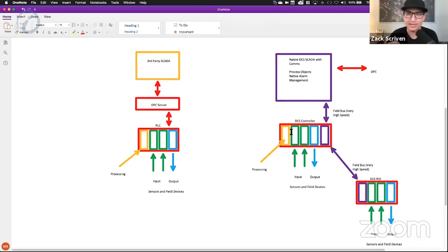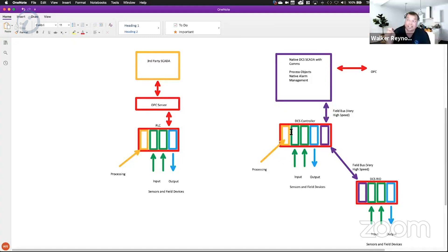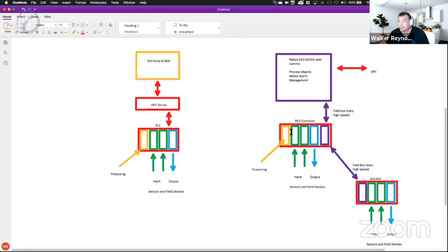This is why some would say that PlantPAx — Rockwell Automation's line of PLCs — makes it DCS-like, because they give you those pre-configured objects that map to their SCADA, to their PLC, and to the real object. That is exactly what Rockwell was trying to accomplish when they created PlantPAx. But the thing Rockwell is missing is that it doesn't natively use a fieldbus to talk from PLC to PLC — that's not how they natively communicate.